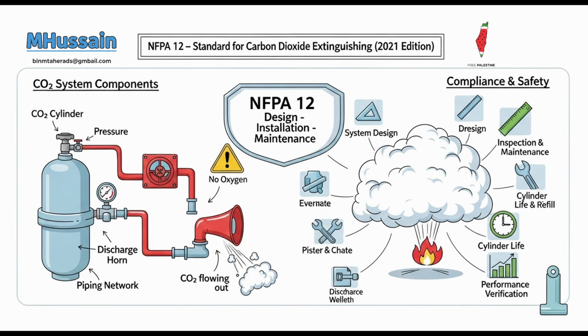Beyond the atmospheric threat, direct contact with the liquid CO2 or the dry ice snow that forms can cause severe frostbite due to its extremely low temperature. Right, that minus 109 degrees Fahrenheit. Exactly. The standard even notes that the discharge of liquid carbon dioxide can produce electrostatic charges, which, under certain conditions, could create a spark. A spark from the CO2 itself. Potentially, yes. So designers must account for these immediate and profound risks to human life, making human safety the paramount concern. That's a huge aha moment for many people, realizing the direct danger beyond just the fire.